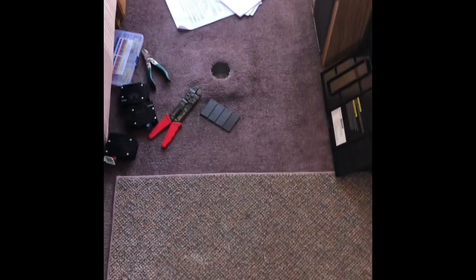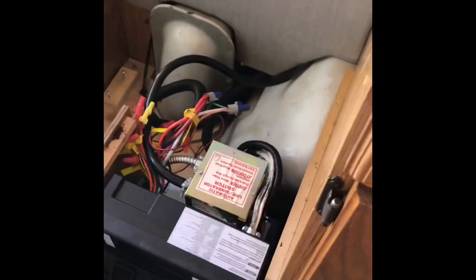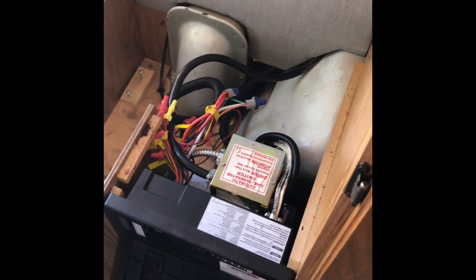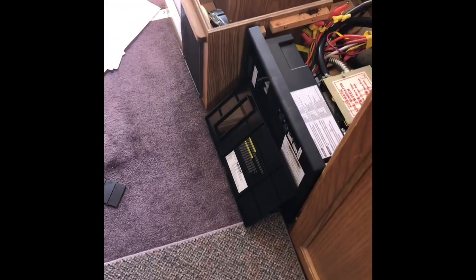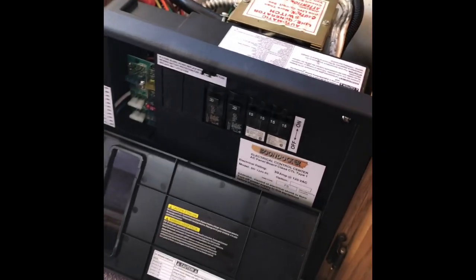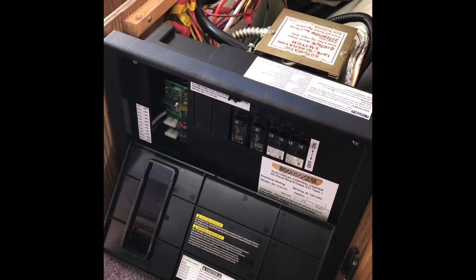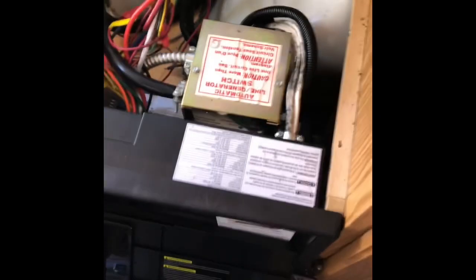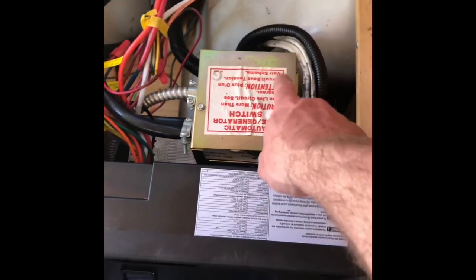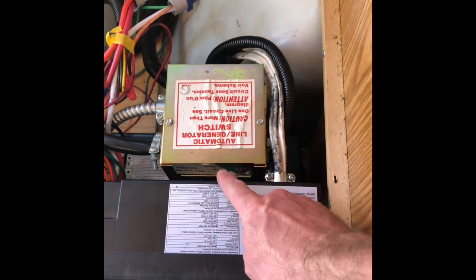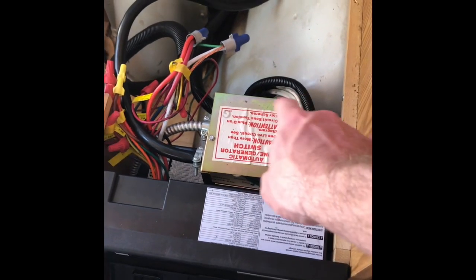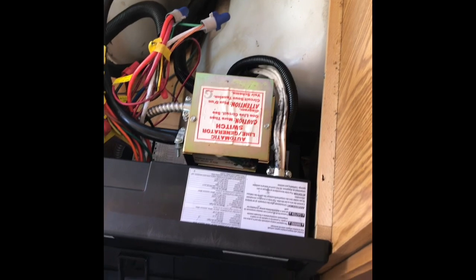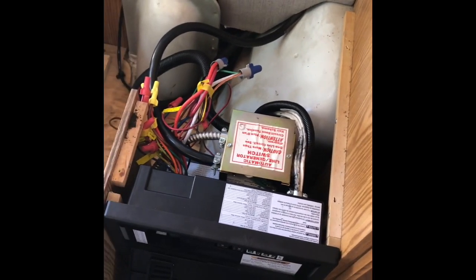Okay, to finish the process up, I just went in and put the cover plate on. Before I actually mounted the last screws, I went in with a shop vac and cleaned up all the old wire clippings and everything else, cleaned up back behind there, taped up the wires, made sure everything looked clean. Don't want to leave all sorts of stuff all over the place. So got the cover on, the breaker's in, we functional tested everything, and from what we're seeing right now, everything's good. So got the automatic line transfer switch on there. I actually turned the cover plate around because where we mounted it didn't actually clear that, so I just turned it around. May go in there and hack off part of it later, but for now it's working. So get the cover put back on, and everything buttoned up, and we are all set.